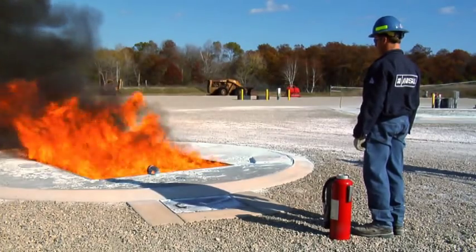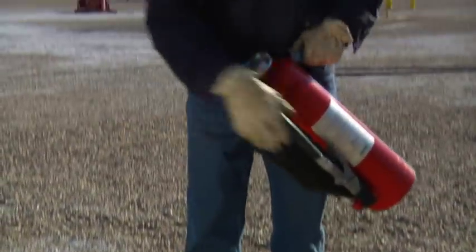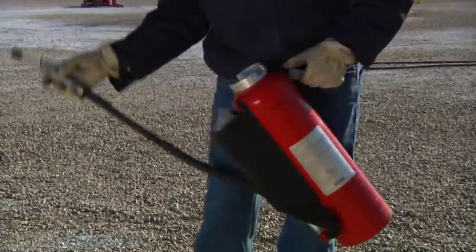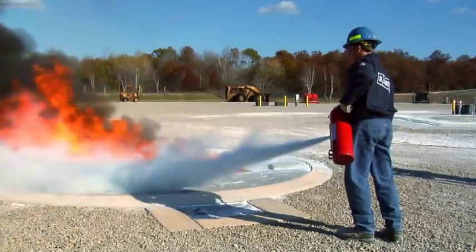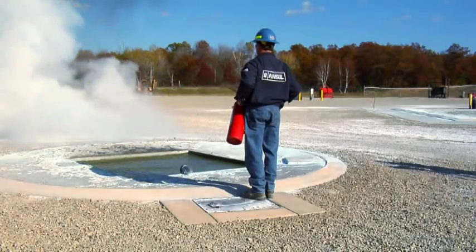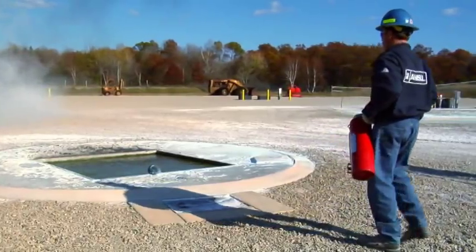To use a cartridge operated extinguisher, pick up the extinguisher, remove the nozzle from the nozzle holder, and push the lever down to pressurize the extinguisher. Position yourself upwind, open up the nozzle by depressing the handle, and make your attack sweeping side to side from the front edge to the back. Once the hazard is contained, shut off the nozzle and carefully back away.